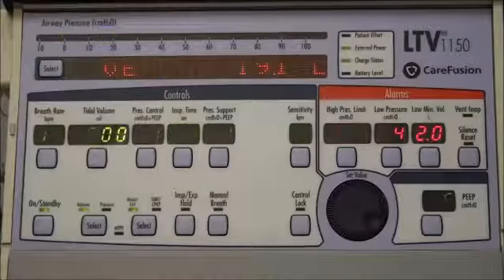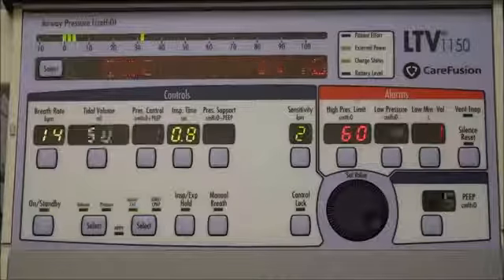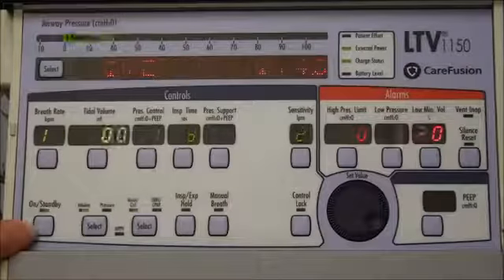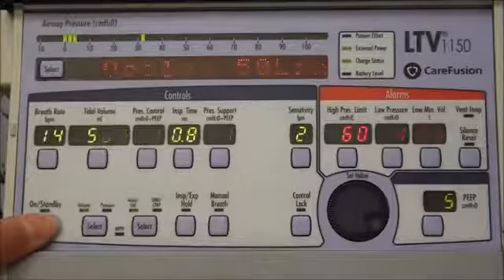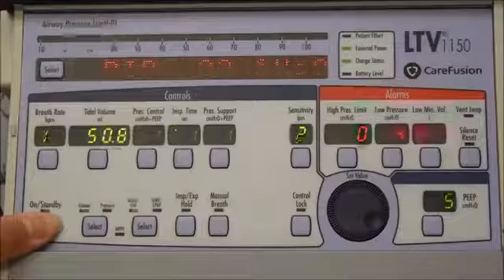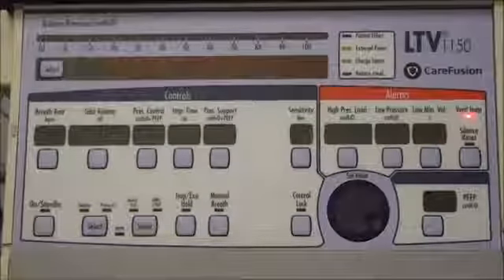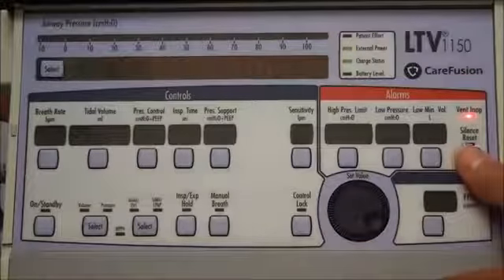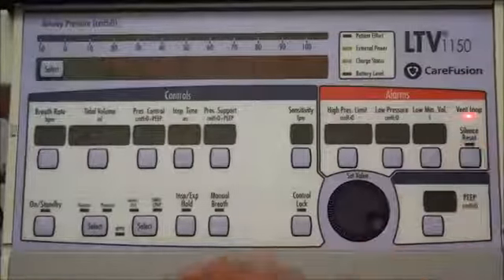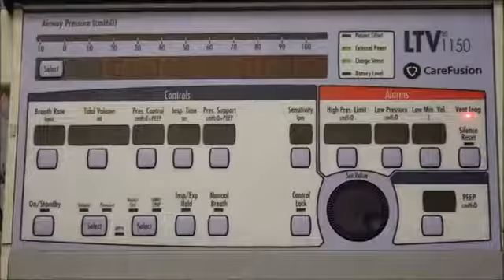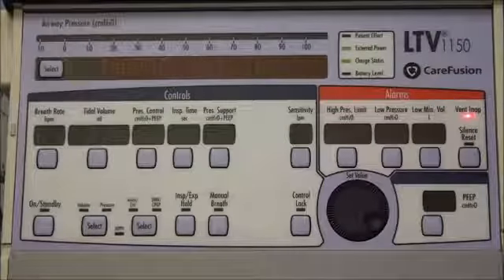Okay, so now I'm going to show you how to turn the ventilator off. What you'll want to do is come back over here to the on standby button. You're going to push it and you're going to hold it in. And then when the ventilator is off, it's going to give you that alarm and you need to come over and hit the reset button. And then you'll notice your Vent Inop light is on. That's perfectly normal. It will do that anytime you shut the ventilator off.